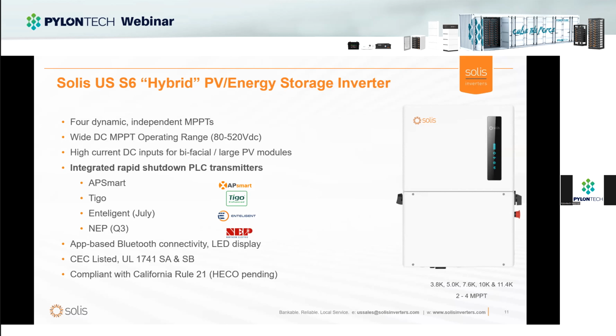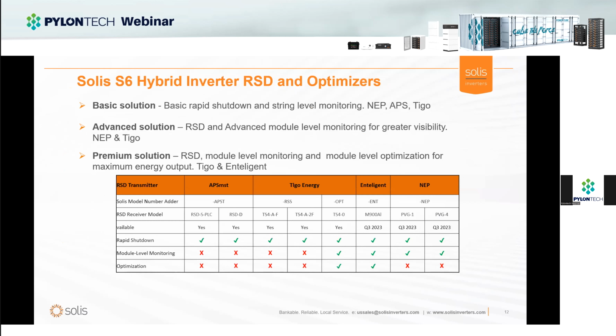It's really kind of fun with the controls and capabilities you now have with these inverters and reliable battery sets that give you a lot of power without needing such huge wires. At high voltage there's a big advantage—you don't have to use as big of wires. As Pat said, you just have positive and negative, plus a CAN bus or RS-485 connection to the inverter. You just tell the inverter what battery you're using, and you're basically done as far as commissioning goes. That's always something I worry about with installers used to easy grid-tie commissioning—it's a bit more involved with a battery, but not with Solis and Pylontech. You can commission these systems in less than 15 minutes.